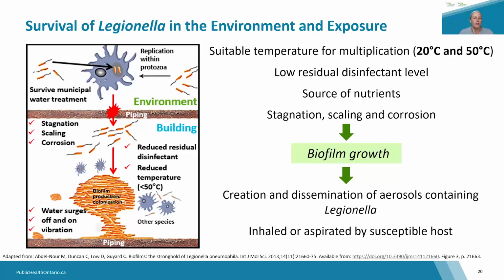Legionella can enter water systems in a variety of different ways, often from external disruption to the system. Depending on the type of system, this can come from things like construction work, like a water main break, any repairs to the system, or even changes in water pressure.